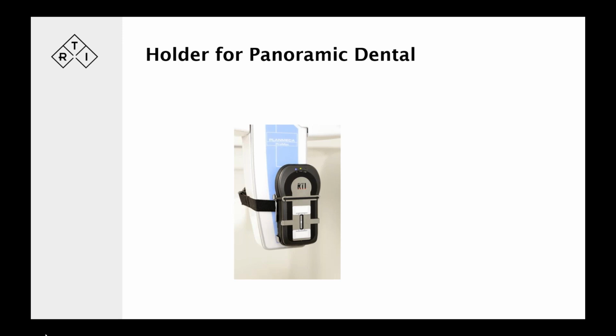For dental, panoramic dental is a bit of a squeeze. Well, we've designed one holder for the Piranha. It's with a strap. There's a suction cup in the back to keep it in place. So there's a strap to fix it into place. Here you've got some fluorescent tape to help you position it sideways, and we found that it's reasonably easy to get that into place. We've done some adjustments to it. If you look from the backside, we can slip the strap into some slots on the rear. That makes it easier to fit it on the corner, as some manufacturers have their detectors quite close to the corner or the edge of a detector panel, and by being able to move the strap to different places, we can get a more stable positioning of it in many cases.